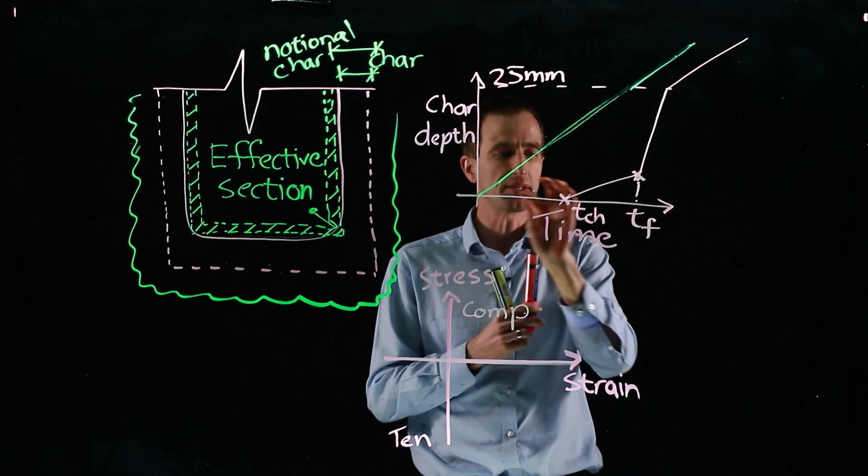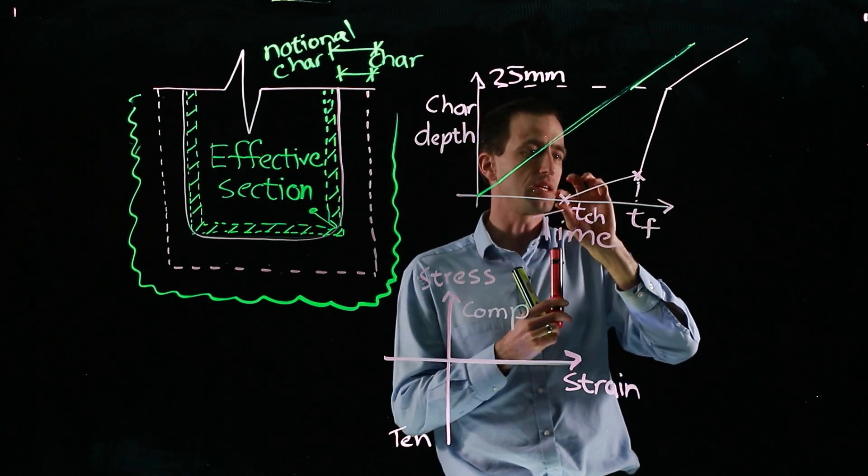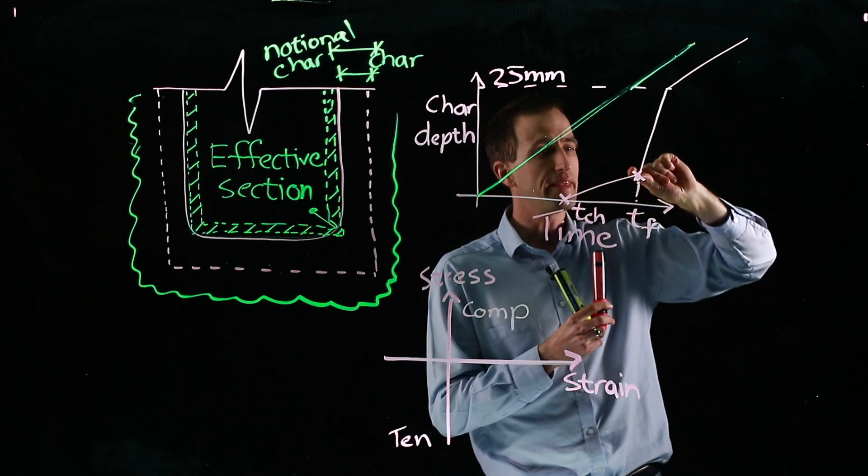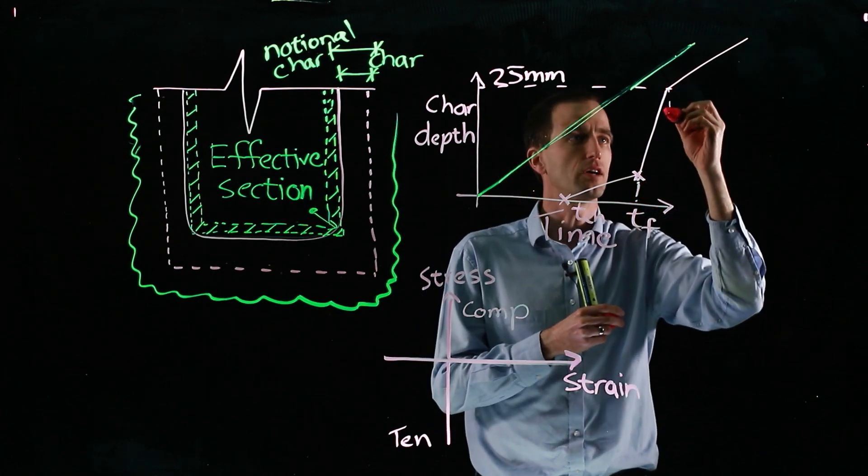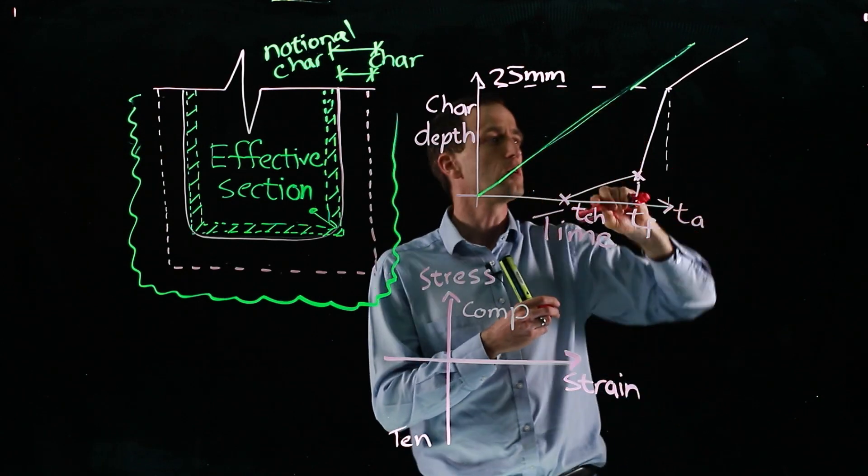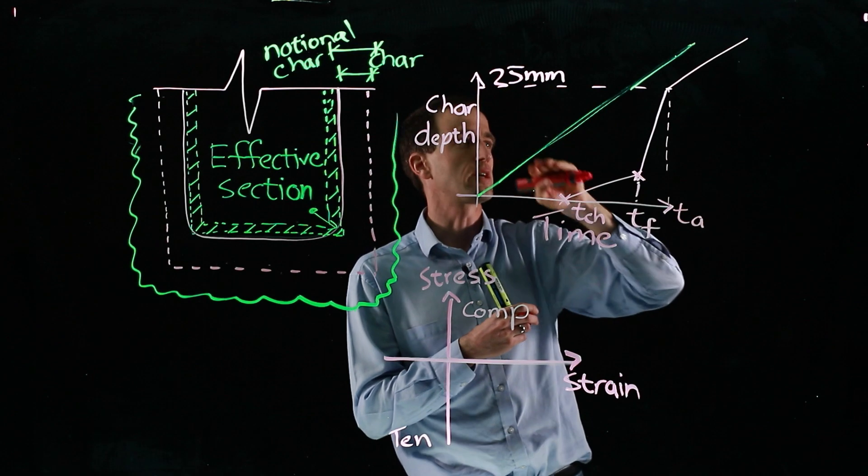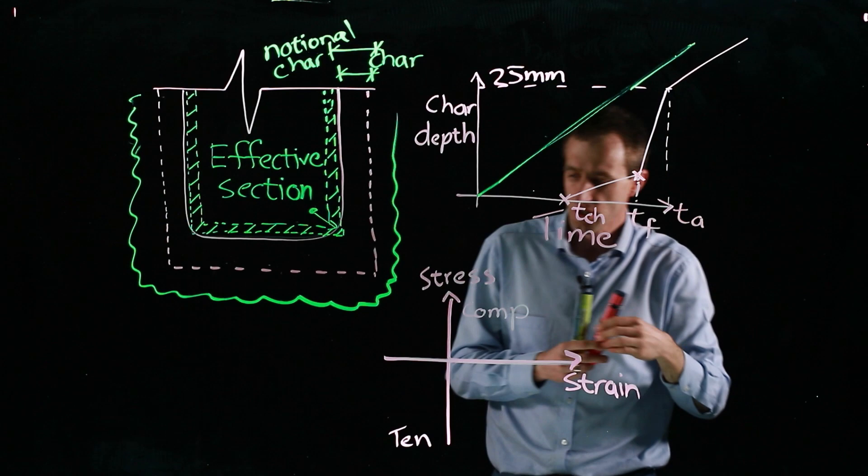So that gives an overview. Initially, no charring. And then the board is still in place, but the charring rate is slower. And then board falls off, it fails, time of failure, then it goes up until we have our layer at time TA, where it reaches a char depth of about 25 millimeters, and then it continues on at roughly the same rate.